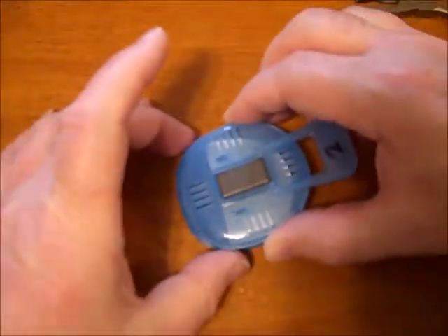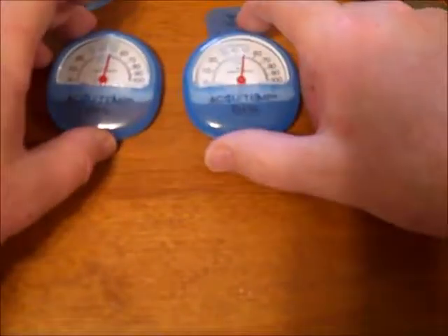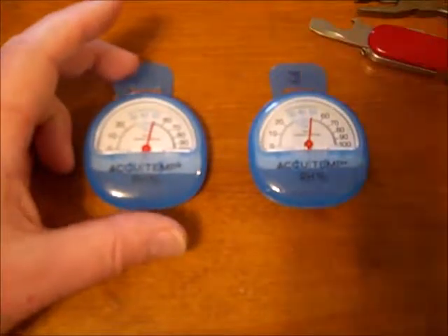For mine right now it's 49%, and drop that back in. There are two little pins to put in place. Put the bottom in and then snap the tops in — and there it is set at 49%. I just did another one at 49% as well. So I'll let those sit and stabilize, then I'll run through another calibration with them to see if they stay the same.